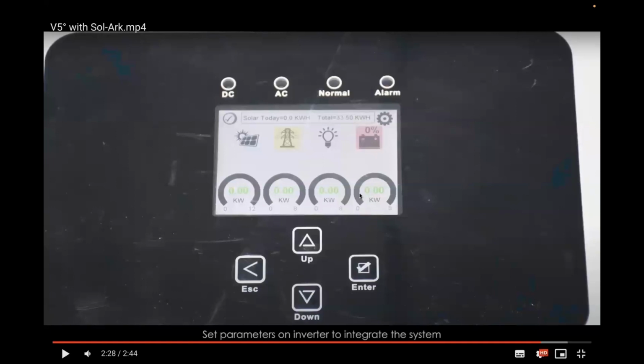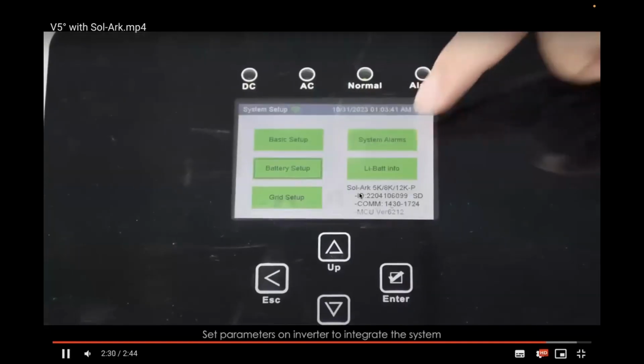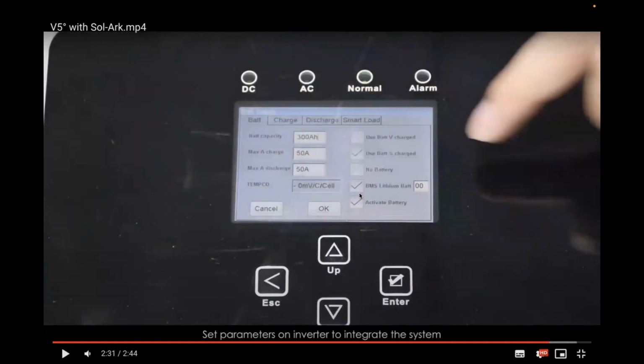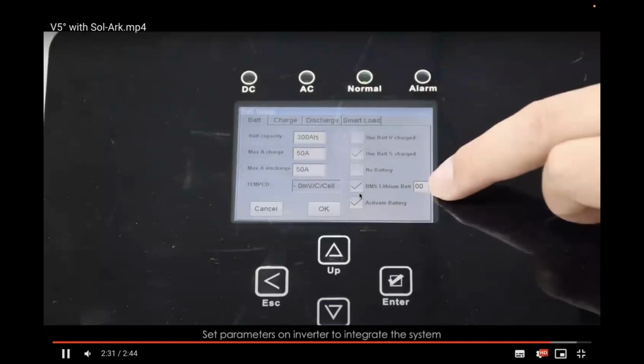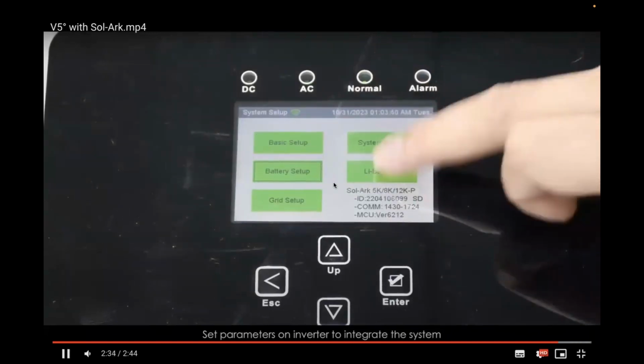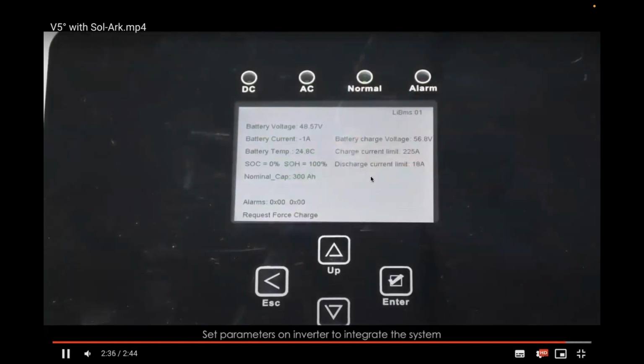There's just a few things we need to program. The closed loop communications programs the inverter system itself, but we also need to change things like how many batteries are in the total battery bank. It's at 300 amp hours because there are 3 of the V5s. And right there, that shows we're communicating directly with the inverter system, which is what we want to see.